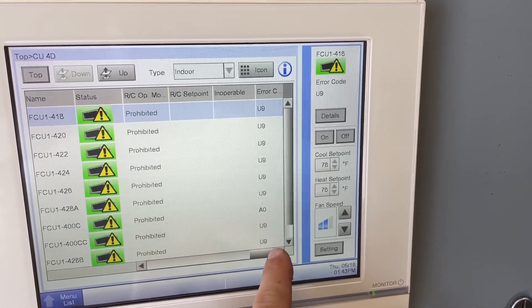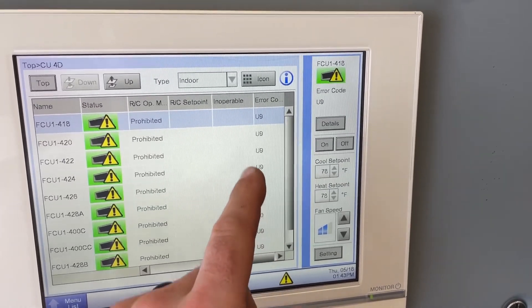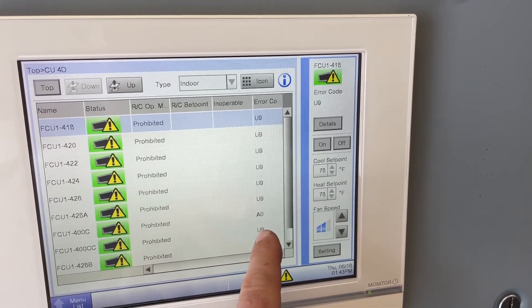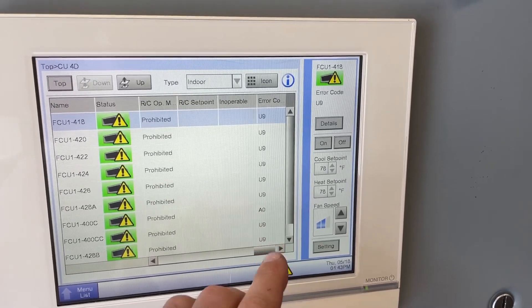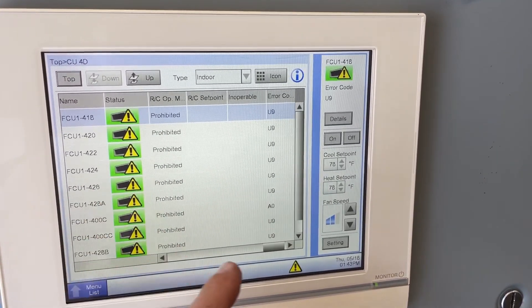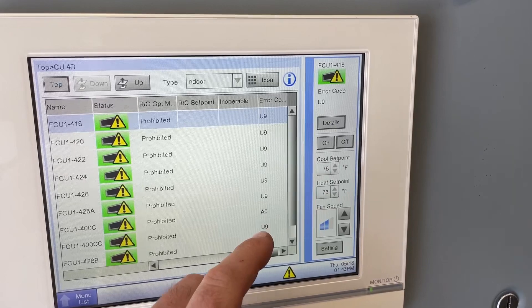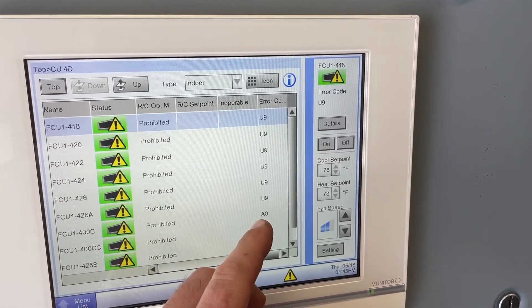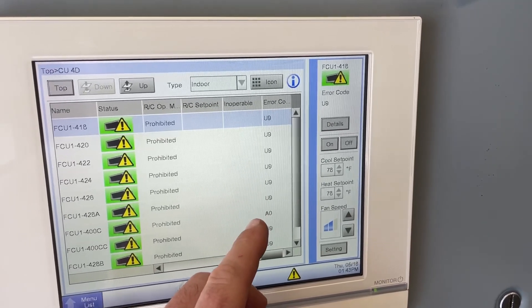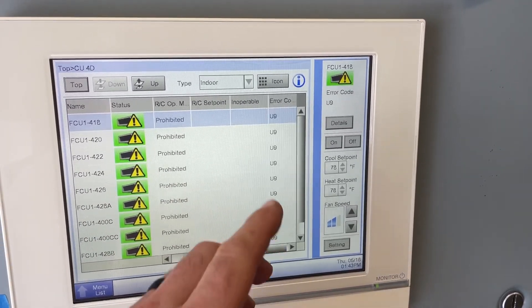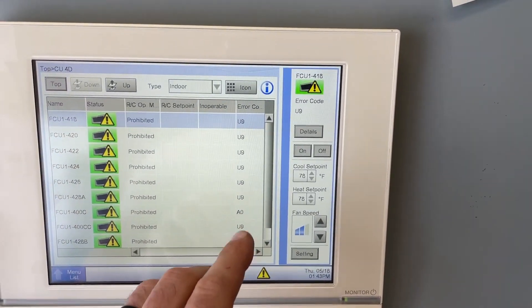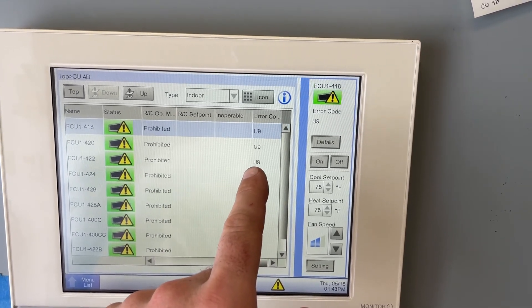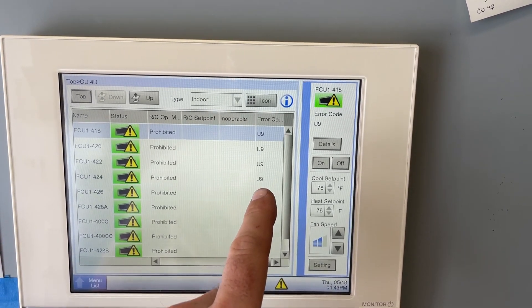That is annoying, and I can't drag the bar. So I've got a U9 and an A0 here. Whenever there's a lot of weird stuff going on, I typically focus on whatever I think is the brunt of the problem, and then it's possible some other things might clear themselves up once we get this taken care of. But this has to do with a communication fault between the indoor and outdoor units.